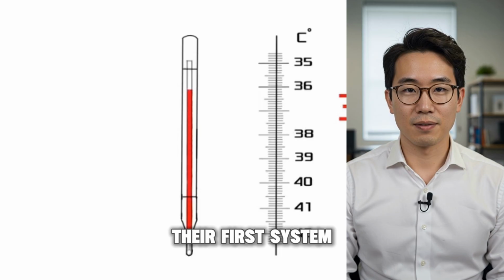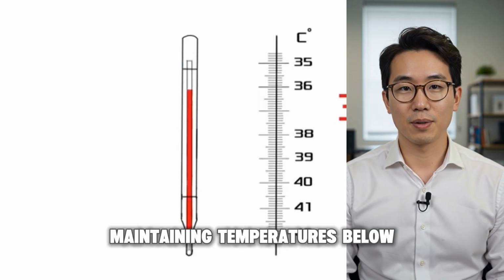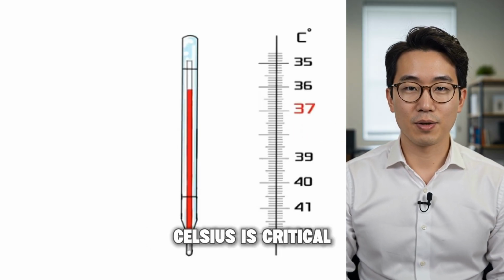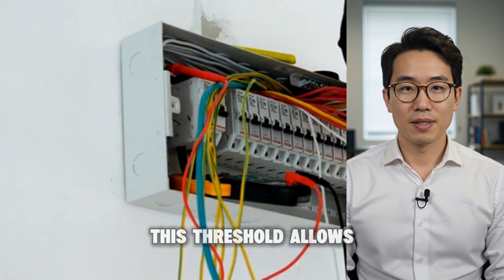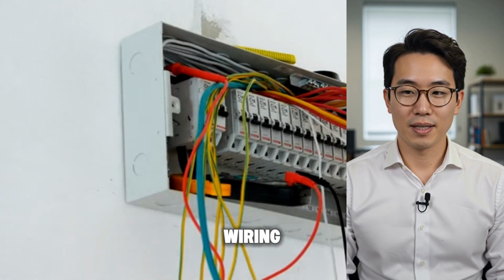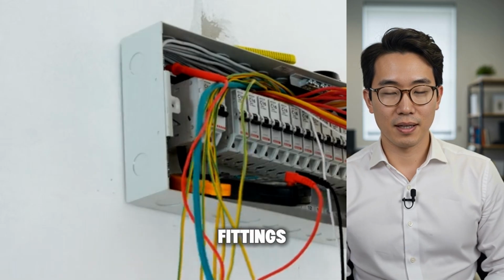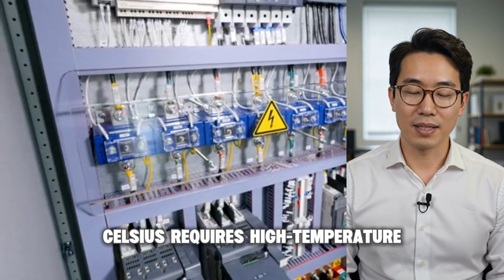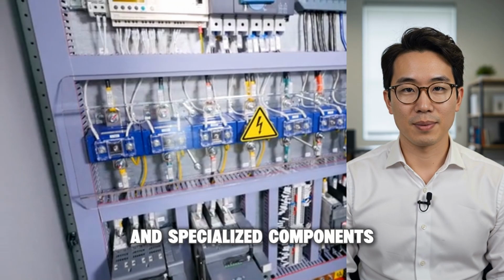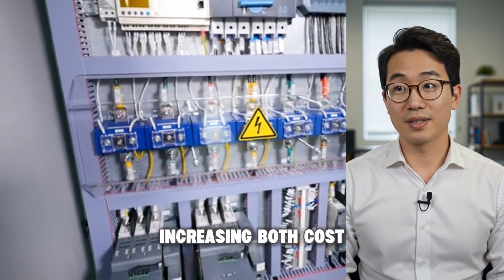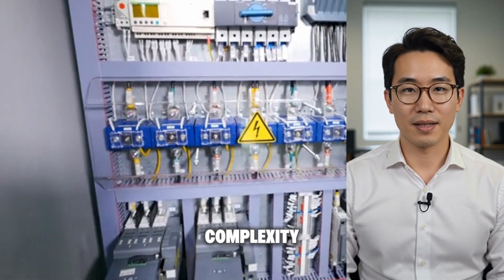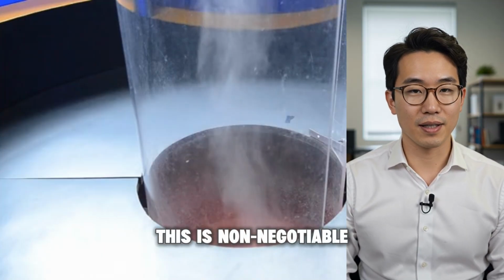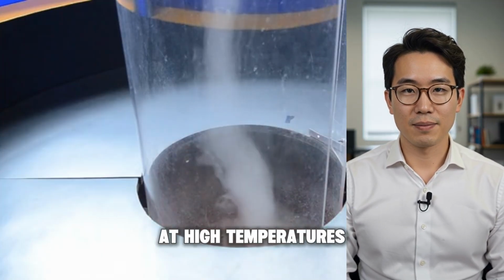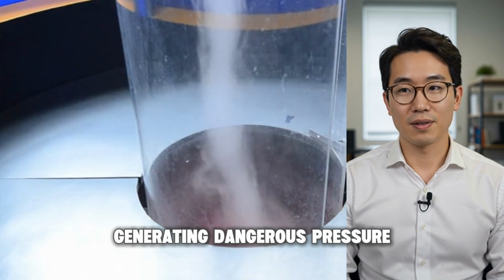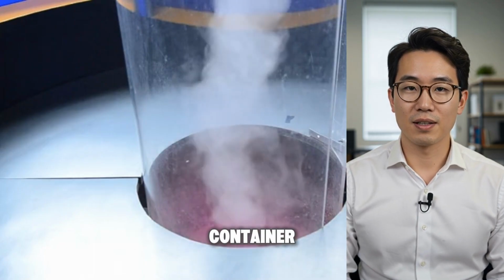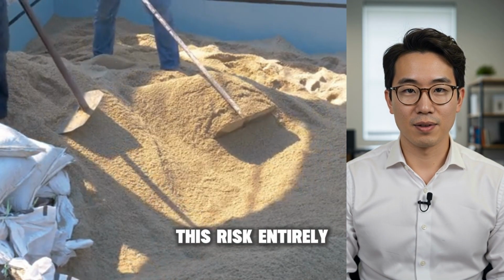For anyone constructing their first system, maintaining temperatures below 150 degrees Celsius is critical for safety. Operating below this threshold allows the use of standard wiring, insulation, and plumbing fittings. Exceeding 200 degrees Celsius requires high-temperature wiring, refractory materials, and specialized components, significantly increasing both cost and complexity. The sand must be completely dry. This is non-negotiable. Moisture in sand at high temperatures turns to steam, generating dangerous pressure within a closed container. Using dry silica sand eliminates this risk entirely.